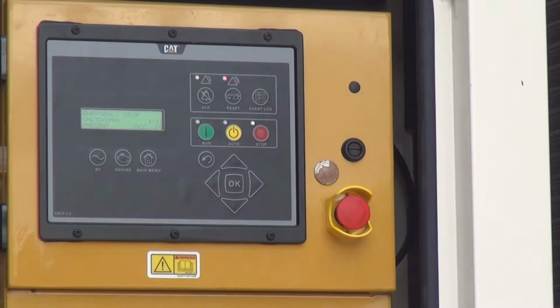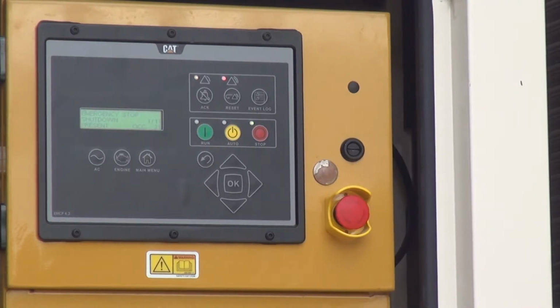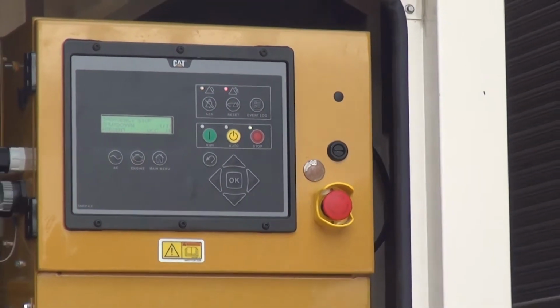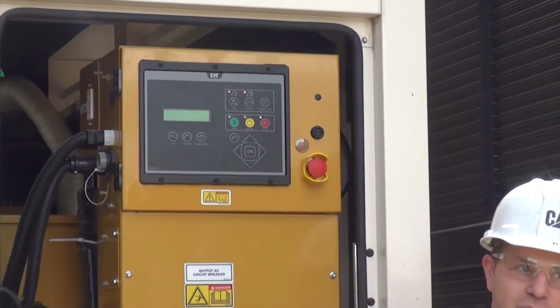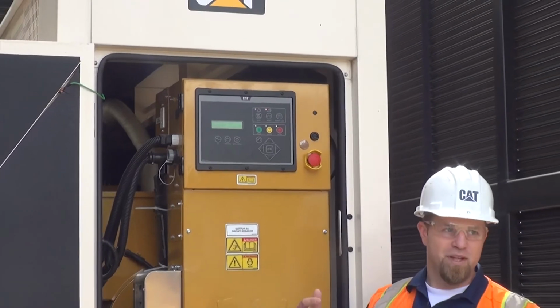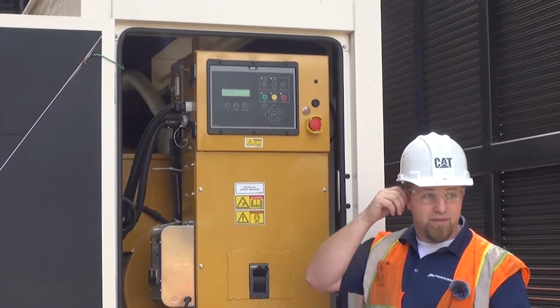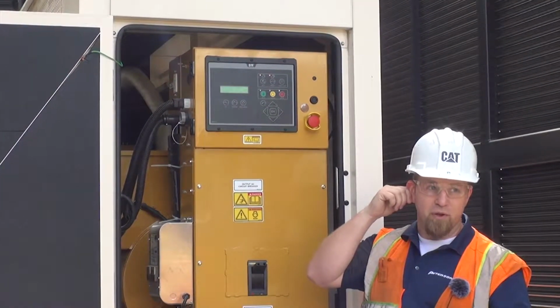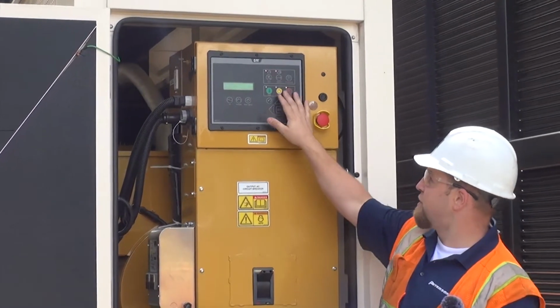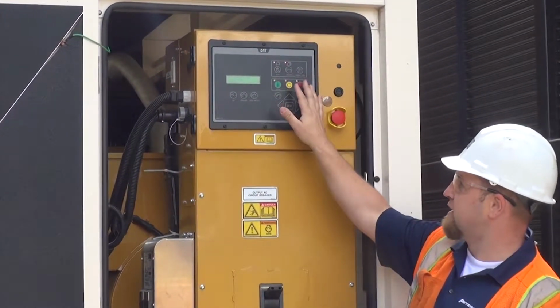So if you were able to reset it in auto—and this is more for some of your older units—you leave it in auto, go top off the coolant, and the second it gets above that sensor, it's going to restart on you again. You wouldn't want to be near a fan blade with it starting up on you and going under full load.